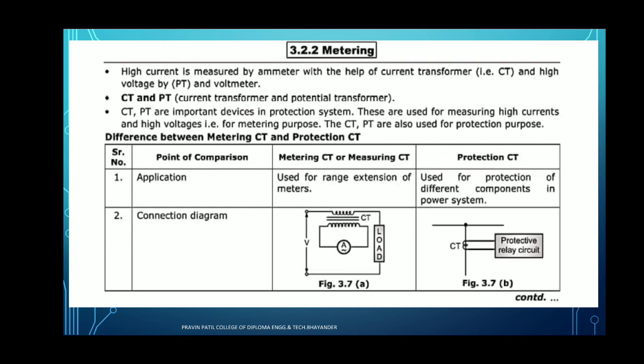The application is for range extension in one case, and for protection of the different components in the power system in the other. Then we have to see the connection diagram representation of the CT. Here in the protection CT, the relay is the main protective device, as the relay directly gives a command to the circuit breaker. Relay is the protective device. As the fault occurs, the alarm buzzer operates with the help of the relay, and then it gives a command to the circuit breaker. The circuit breaker is the device which isolates the fault and provides protection to the power system in the protective systems. So these are the main differences between the metering and measuring CT as well as the protective CT.